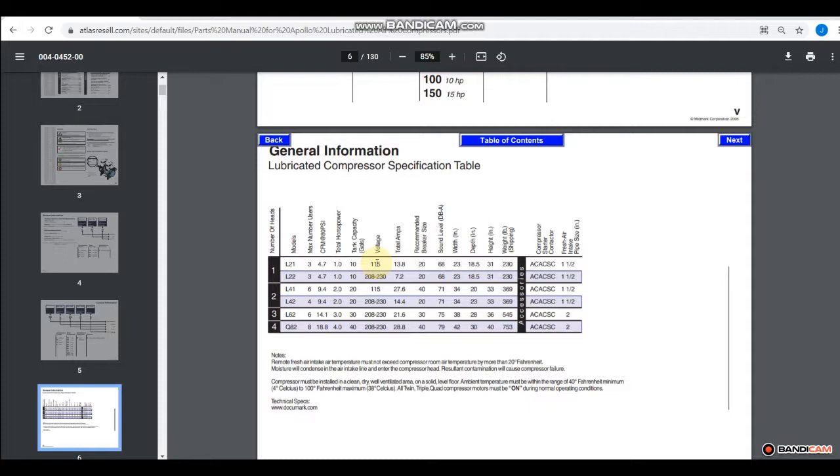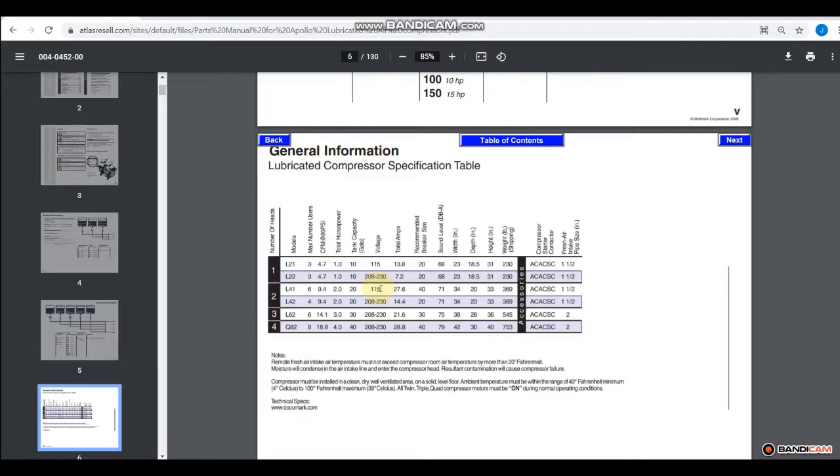Now the voltage here, all but two are 208 to 230 volts. And only two are 115 volts. And those are the L21 and the L41. So you have basically a single head that's 115 and a dual head that's 115. But after that, it's all 208.